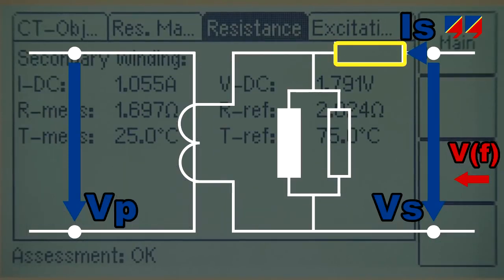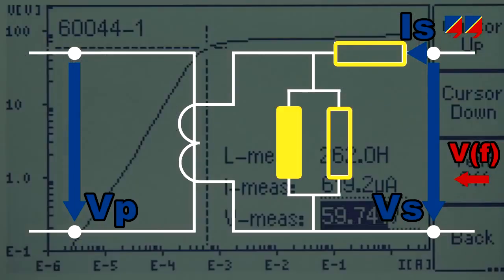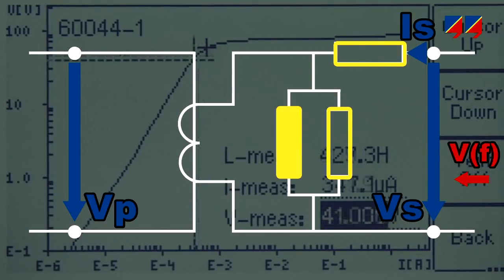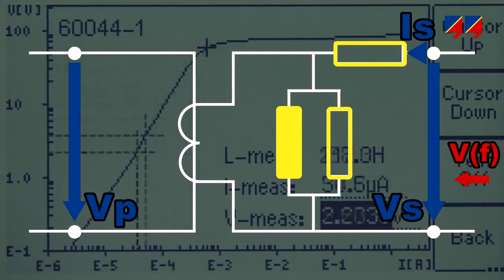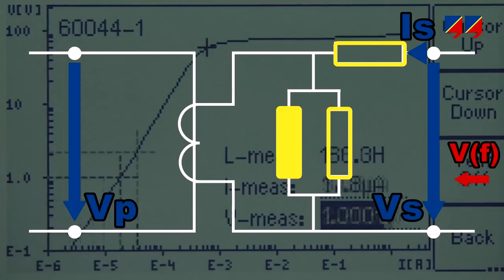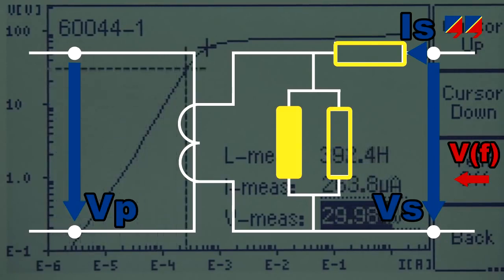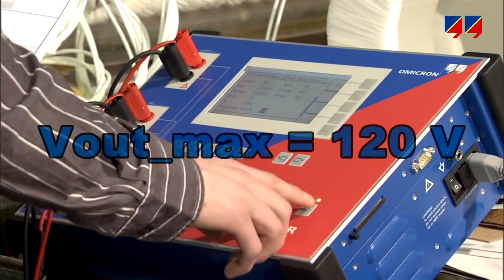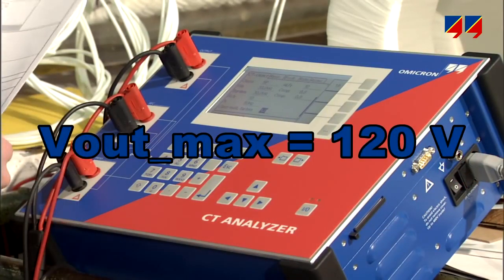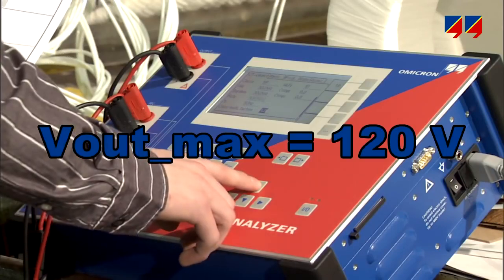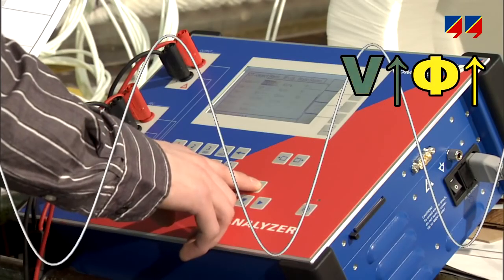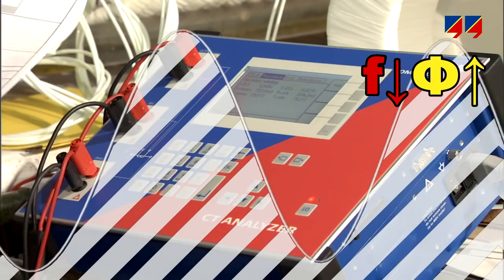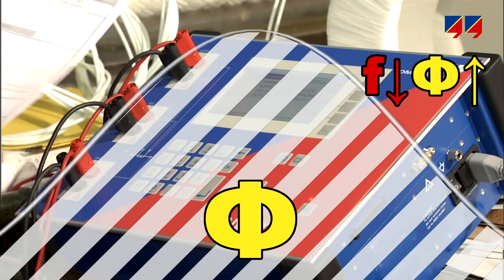First, it measures the DC resistance of the CT's secondary winding. Then, knowing the DC winding resistance and the corresponding voltage drop, it measures the excitation curve to determine the magnetic characteristic of the core. CT Analyzer performs the excitation curve measurement with safe low voltages of up to 120 volts, reducing the frequency instead of increasing the voltage if higher magnetic flux is required.